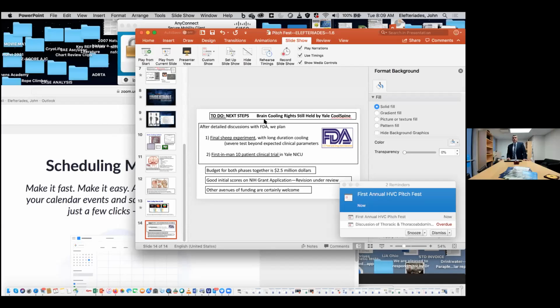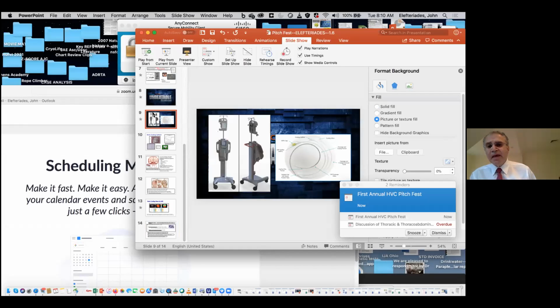And maybe a quick follow-up, Dan, if it's okay. What in the catheter, in the structure and the engineering of the catheter, what safeguards have you put in place to prevent the cooling to go below 18 degrees or whatever threshold you'd like to set? There are tremendous safeguards. That device that I showed you has safeguards against excess pressure, against any rupture of the catheter. It very carefully controls flow rate, and it absolutely controls temperature, and it's all computerized.